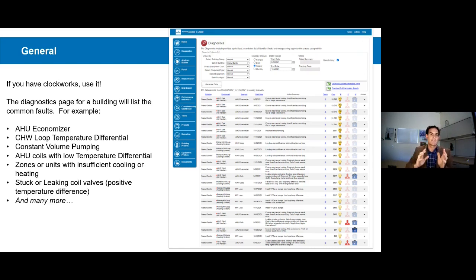It runs diagnostic tests every day, every week, every month, and then it produces this list of faults. And they're sorted. There are comfort faults, there are energy faults, and there are maintenance faults. So you can just download this list and take a look at a month or 2 months worth of fault data from the building, and that'll show you exactly where the problems are in the building. It'll show you which zones, which valves, which coils, and which pieces of equipment are having problems and what problems they are having. Amazingly valuable data.